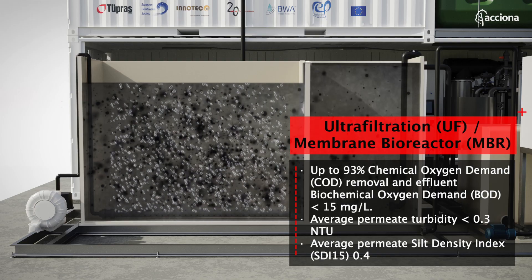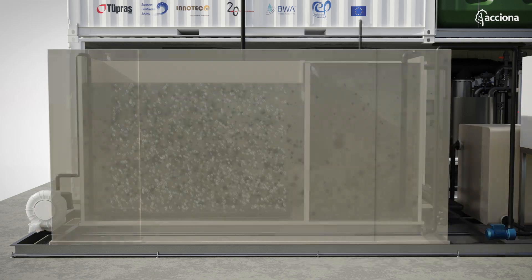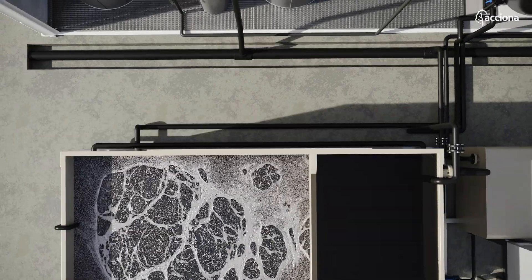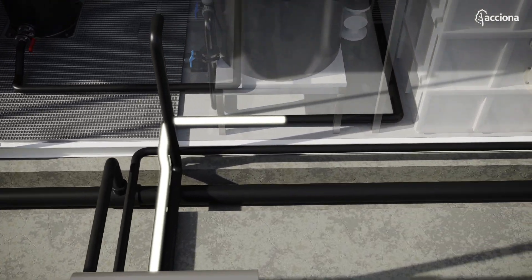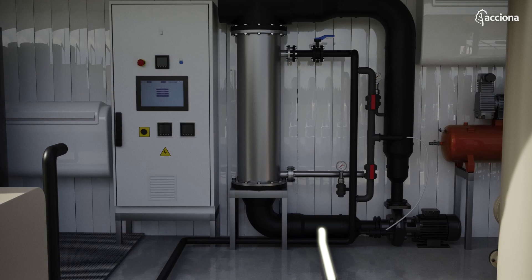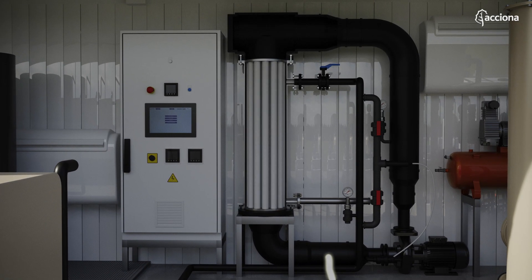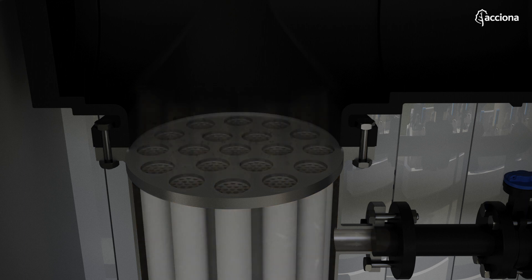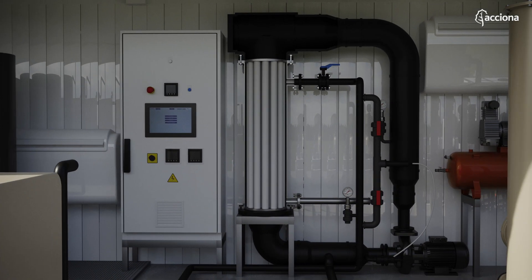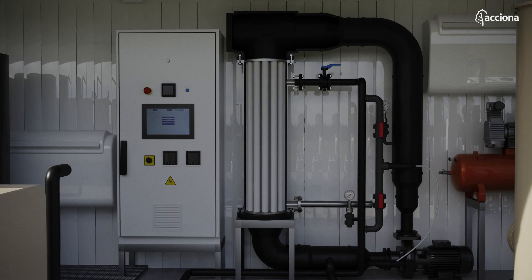Subsequently, water is fed to the ultra-filtration membrane. Water and those compounds smaller than a certain size pass through the pores of the ceramic membranes, whereas larger particles do not, thus creating a high-quality treated water free of suspended and colloidal material in a consistent way. There is a recirculation along the membrane in order to diminish membrane fouling, and also to the biological basin in order to maintain its biomass concentration.